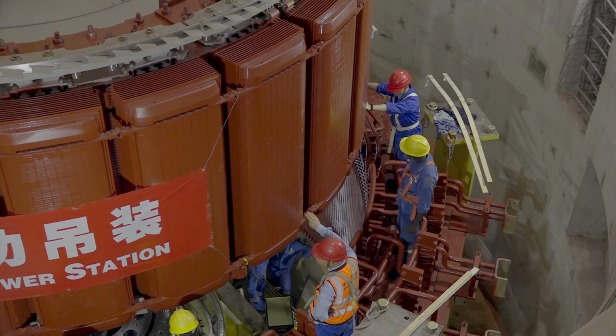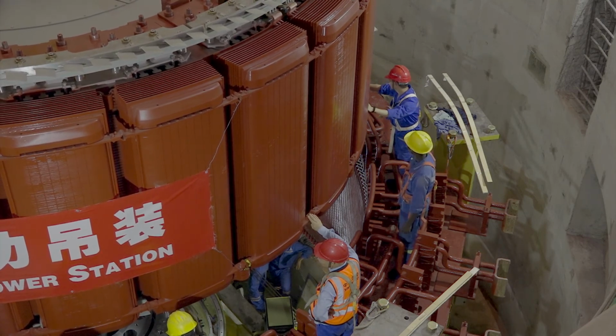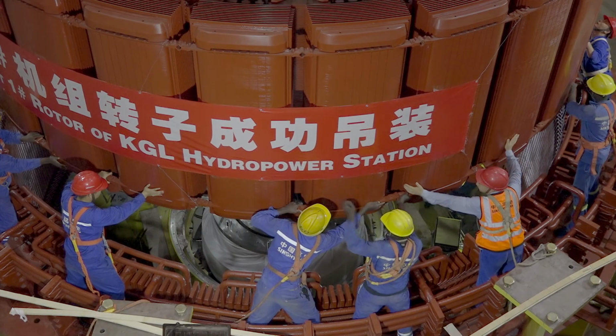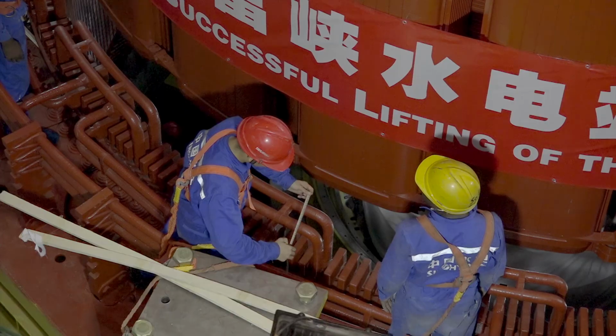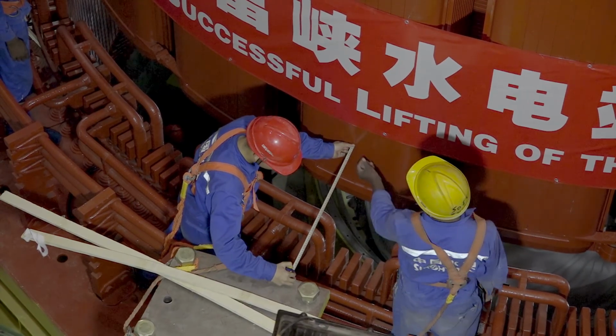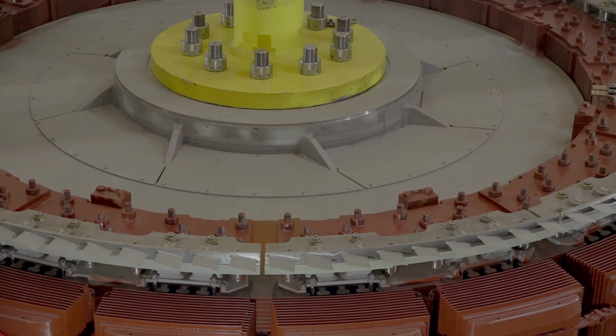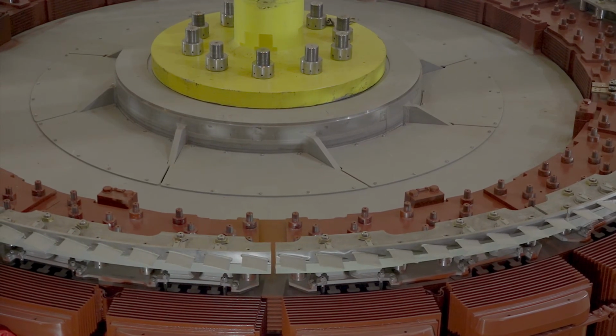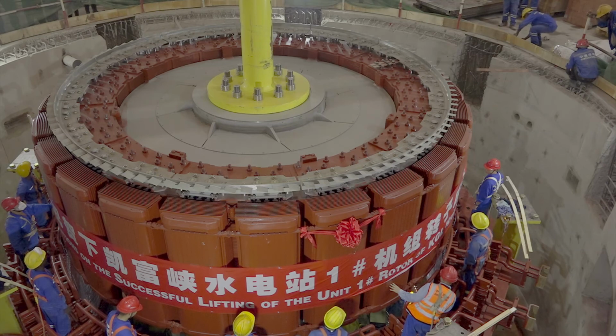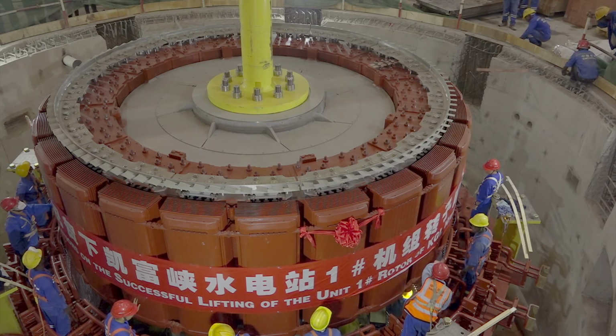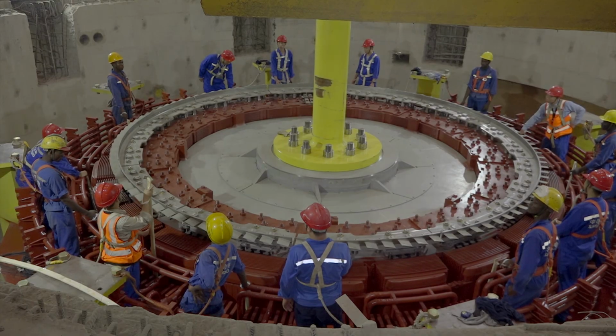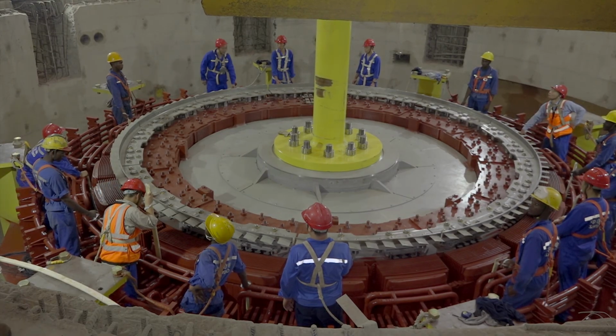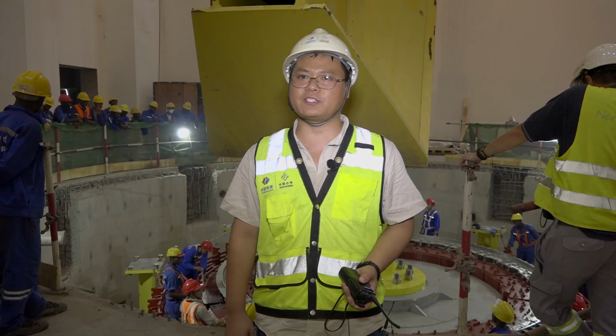So it's a very tight clearance. As we take it down, it is a slow process, because any movement of the rotor hitting the stator would cause damage. With the rotor now lowered, we'll continue with the assembly of the other components below and above the rotor. After loading the rotor, the equipment is almost complete.